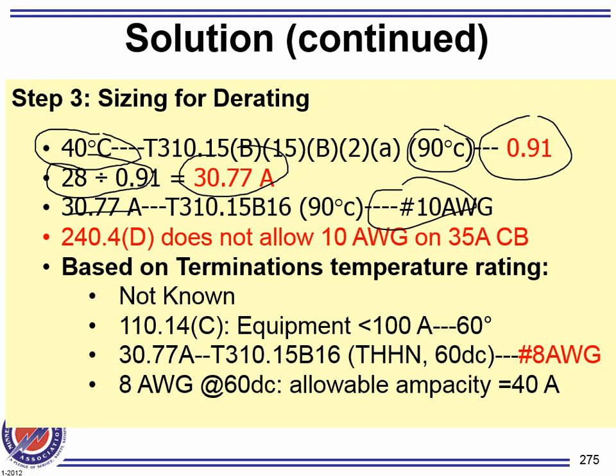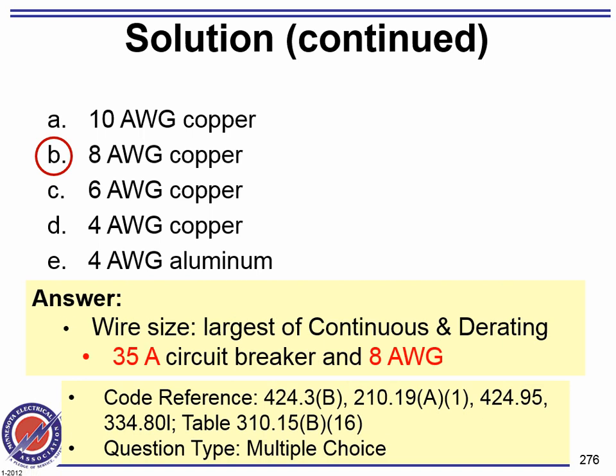What's wrong with number 10? Anyway, your conductor will be based on the termination temperature rating. Your conductor had to be number 8. Your conductor had to be number 8. Number 8. About the ampacity, any comments?